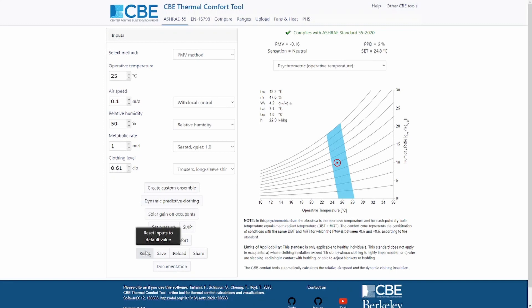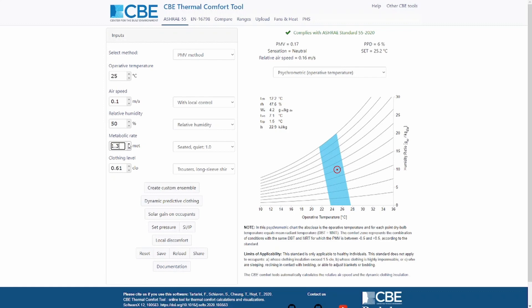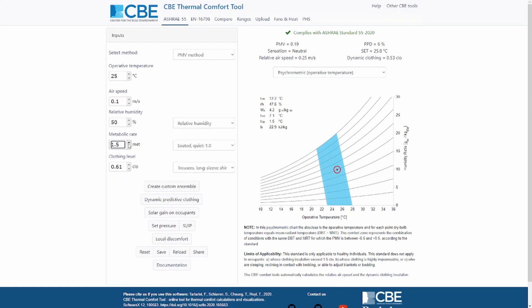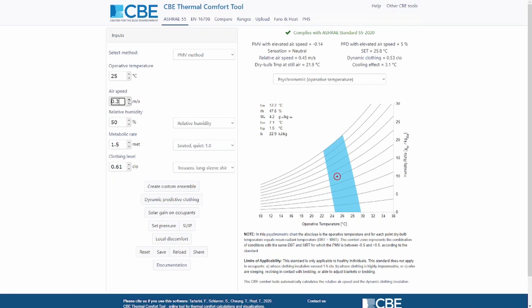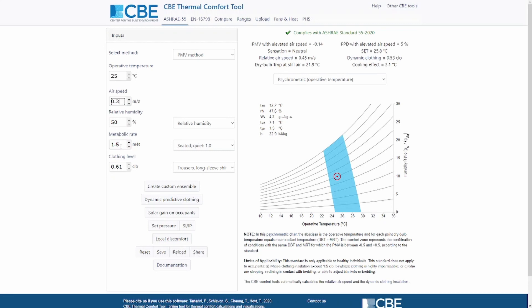Let me show you an example of how the metabolic rate affects the dynamic clothing level and the airspeed. I'm going to increase the metabolic rate and also increase the airspeed to 0.3 meters per second. The tool is telling me that based on this metabolic rate of 1.5 MET, my relative airspeed is now 0.45 meters per second, and the dynamic clothing has decreased to 0.53 even though we entered a clothing value of 0.61 clo, because as the person moves with a higher metabolic rate it pumps air under the clothes, providing less insulation.